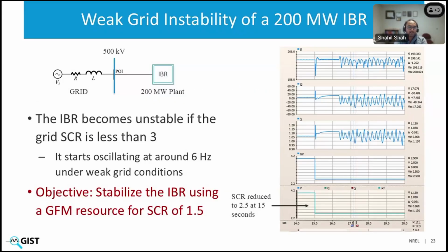So here is a 200 megawatt plant, not those 3 PV plants. This is a different plant. Again, we are using black box models from AEMO, and this 200 megawatt IBR plant becomes unstable whenever the grid short circuit ratio becomes less than 3. And we can also confirm that from this time domain simulation of the plant in single machine infinite bus format, where we reduce the SCR from 4 to 2.5. And then eventually the plant starts oscillating at around 6 Hertz and then trips. So this really shows that this plant cannot operate when the SCR of the grid at the POI is less than 3.